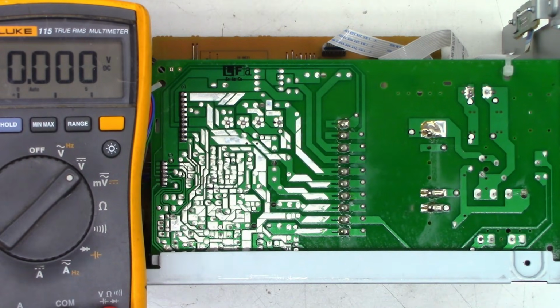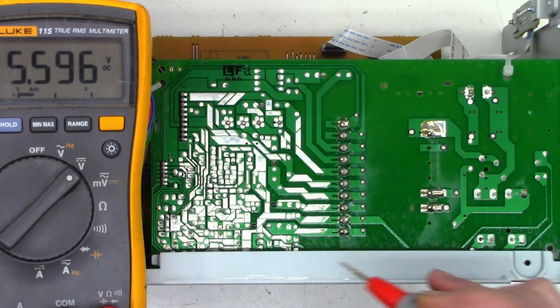This is the voltage side of the relay, and we see 5.6 volts, and when I press the power button it pulls down to 1 volt. This is the control side of the relay, which should pull down to 0 volts, and it pulls down to 0.06 volts. Totally happy with that.